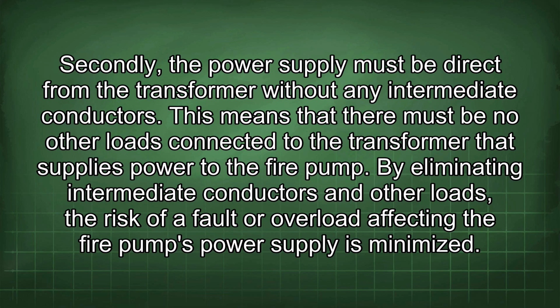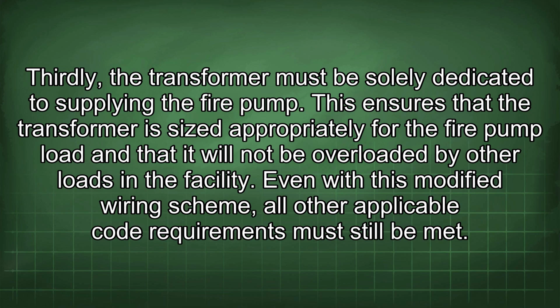Secondly, the power supply must be direct from the transformer without any intermediate conductors. This means that there must be no other loads connected to the transformer that supplies power to the fire pump. By eliminating intermediate conductors and other loads, the risk of a fault or overload affecting the fire pump's power supply is minimized. Thirdly, the transformer must be solely dedicated to supplying the fire pump. This ensures that the transformer is sized appropriately for the fire pump load and that it will not be overloaded by other loads in the facility.